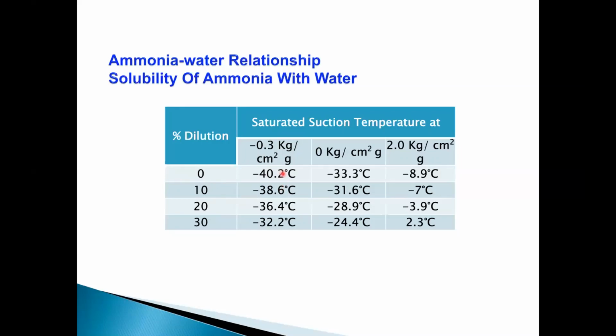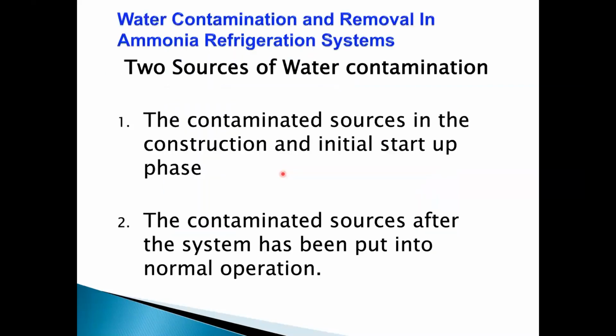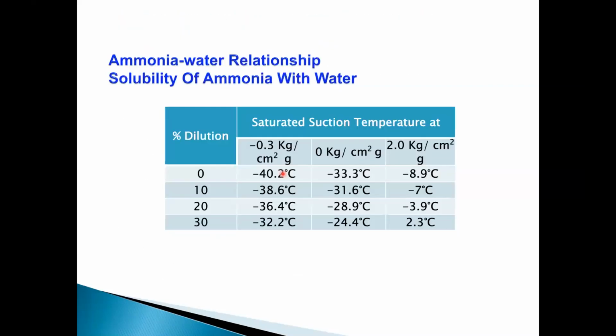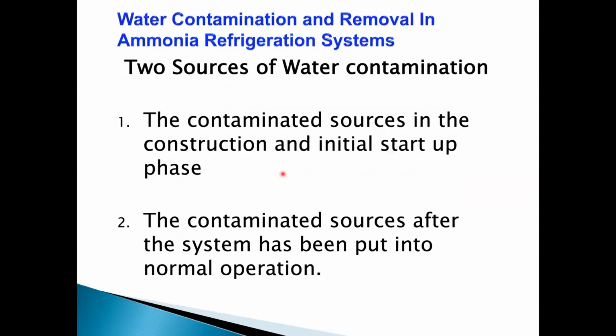It means that to achieve the same temperature, you have to operate at a lower suction pressure, consume more power, and you will also lose refrigeration efficiency. Losing refrigeration efficiency means you run at a higher cost, with more corrosion of ammonia coming into contact, and other effects like that. I will show you what the effects are in the next few slides, and how the water comes in.